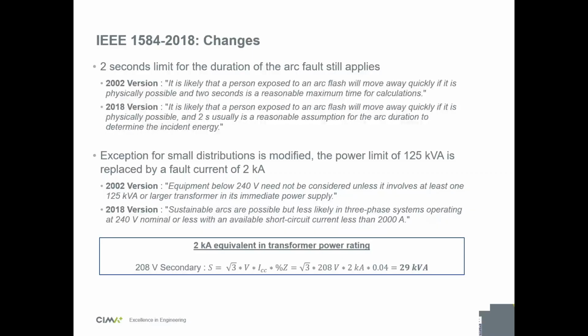Let's say we're trying to find the equivalent of the 2 kA in transformer size. Say we have a 480 to 208 volt transformer with an infinite source above it and an impedance of 4%. What would be the size of the transformer that we could say is the cutoff limit with the new 2 kA? The formula is pretty simple: square root of 3 times 208 times 2 kA times 4%. It comes up to about 29 kVA. As you see, before it was 125 kVA. Now if you convert it to an equivalent transformer, it's 29 kVA. So you go much further down in your distribution. The arc flash studies need to be updated to include all the low power equipment.